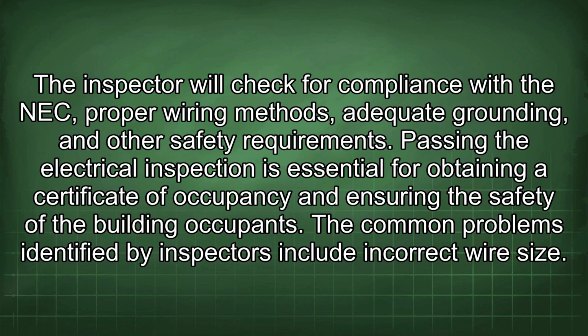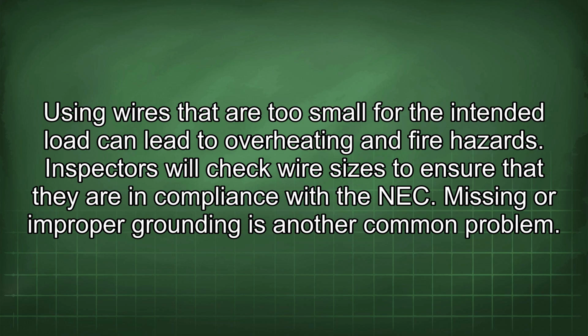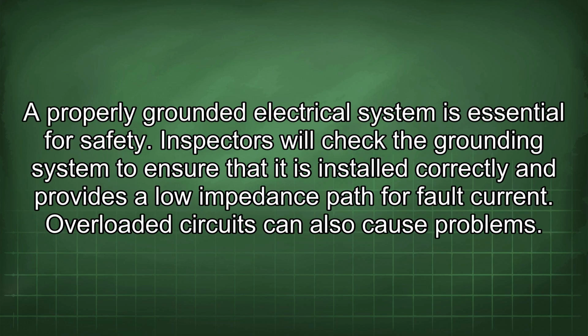The common problems identified by inspectors include incorrect wire size. Using wires that are too small for the intended load can lead to overheating and fire hazards. Inspectors will check wire sizes to ensure that they are in compliance with the NEC. Missing or improper grounding is another common problem. A properly grounded electrical system is essential for safety. Inspectors will check the grounding system to ensure that it is installed correctly and provides a low impedance path for fault current. Overloaded circuits can also cause problems.